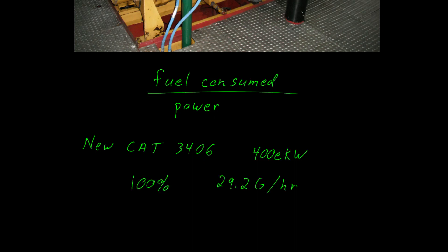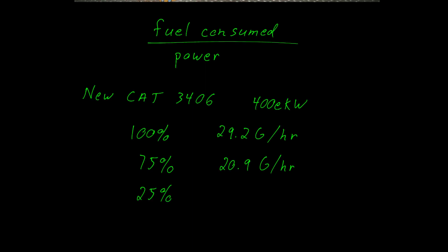At 75% load, 20.9 gallons per hour. And at 100 kilowatts, which is a quarter load, we can expect it to consume about 14.4 gallons per hour.